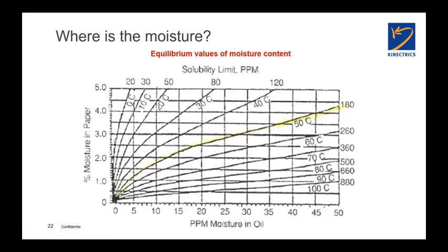And I will tell you, just before I forget, to go back to my example of the failed GSU on the opening slide, that 400 MVA single phase unit. When I got the phone call that day from the utility that they had a failure and they wanted some help in finding out what was going on, this was a Sunday afternoon, I said to the engineering supervisor, Monday morning when I'm in the office, I'll pull the oil test records and we'll take a look. Which I did. And the oil Karl Fischer test, ASTM D1533, showed 8 parts per million of moisture in the oil, which on its own, it's a single digit, right? 8 parts per million. It doesn't sound bad.